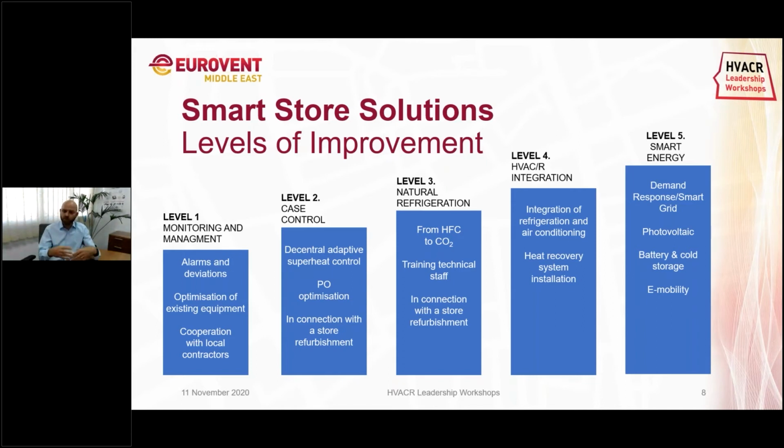Simple. We are expecting that most of the cabinets, they have a small electronic controller able to send basic information about temperature, defrost, and this thing. You might start making use of the management system that you have. And then simply analyze the alarms that are coming, some sensors probably for doors and things, just to start educating yourself of what kind of supermarket I have, where are the alarms coming from, and how I can improve my supermarkets only looking at alarms.